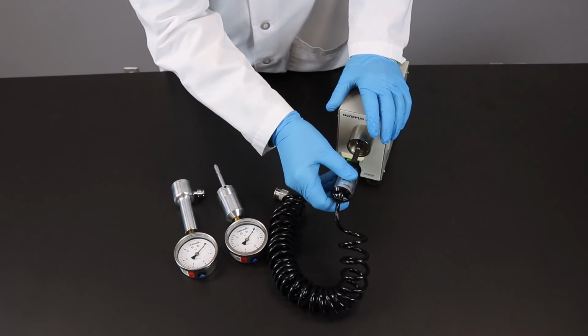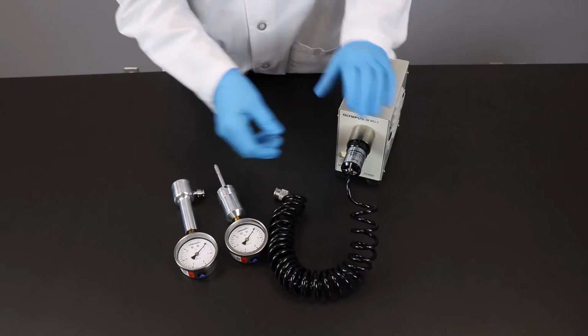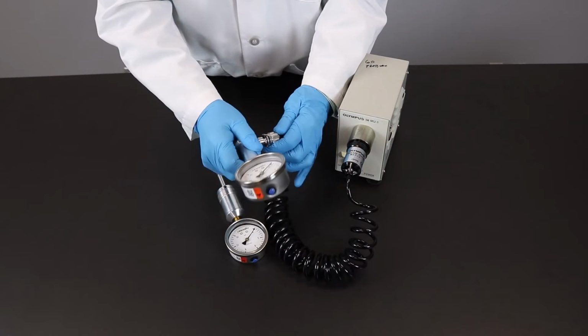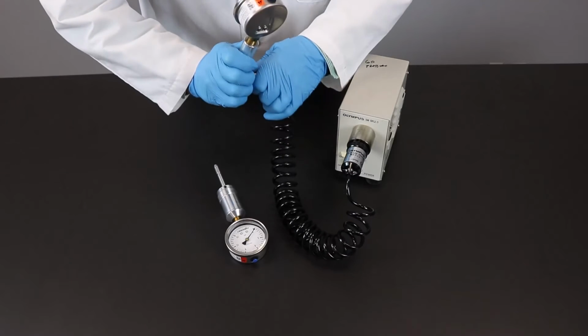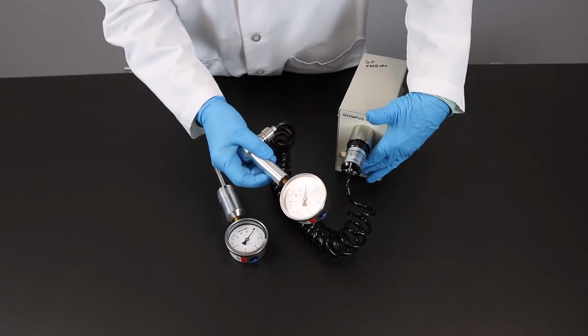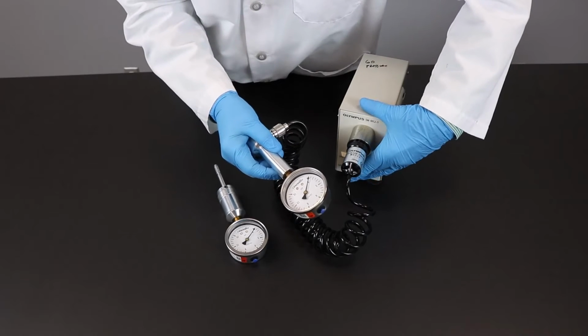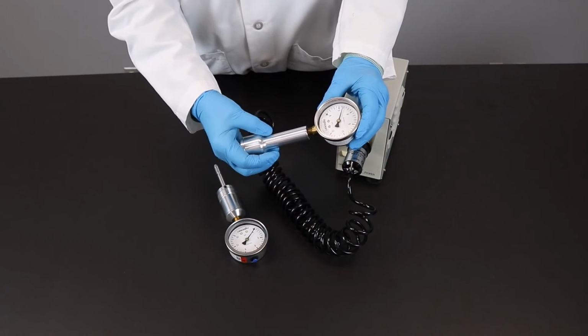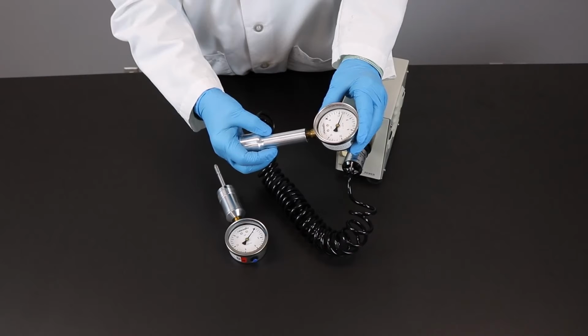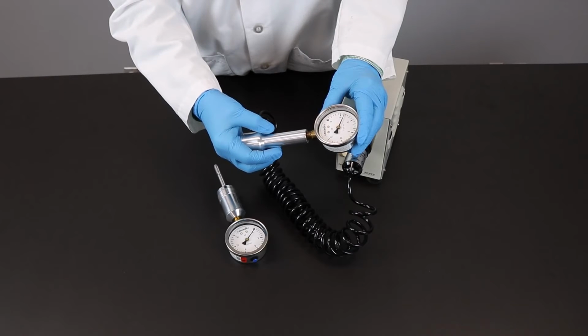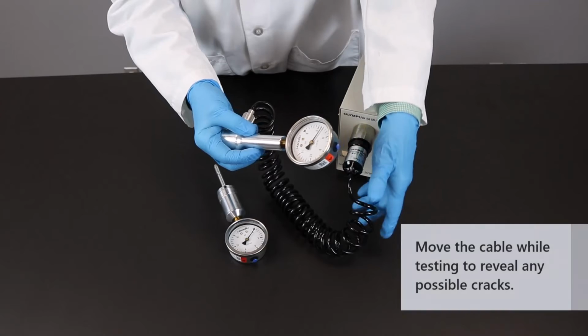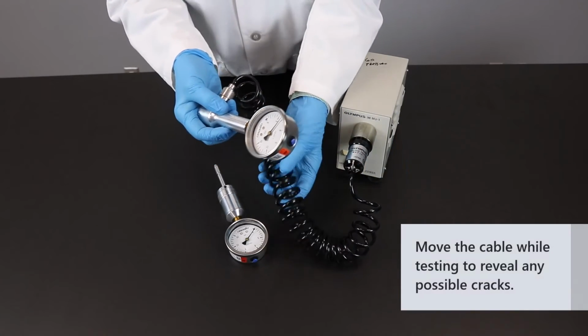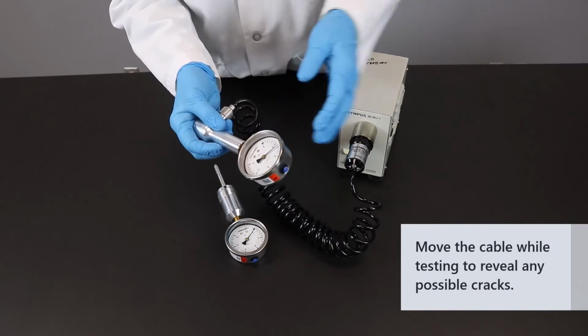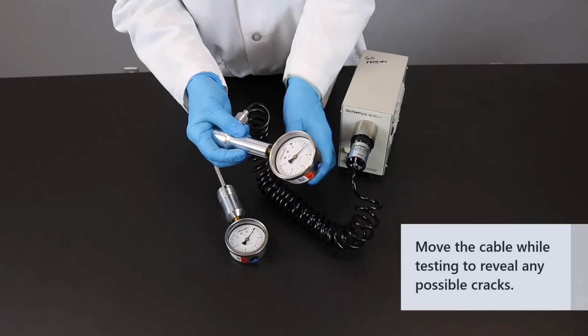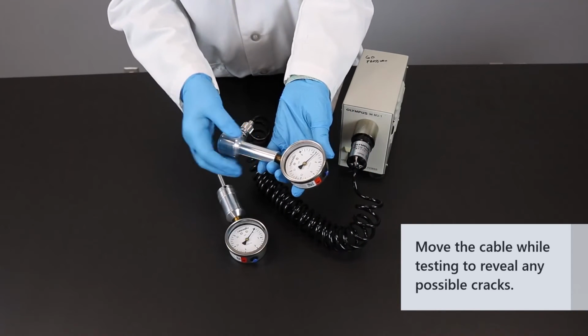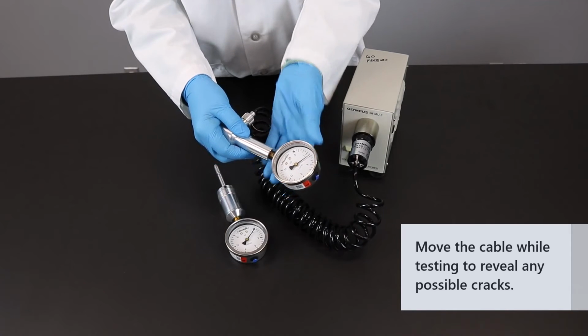The next thing we're going to do is test the cable, because that could fail as well, separate from the base unit. We're going to connect the appropriate leak tester, and we're going to do the same. Turn the unit on and look at the gauge. For this, the cable measurement needs to be between 2.9 and 4.1. You can see that it is. We're going to do it again for at least a minute. What I recommend too is that you move the cable as you do it to make sure you're not opening up any cracks that may exist in the cable, and that the gauge doesn't fall suddenly.